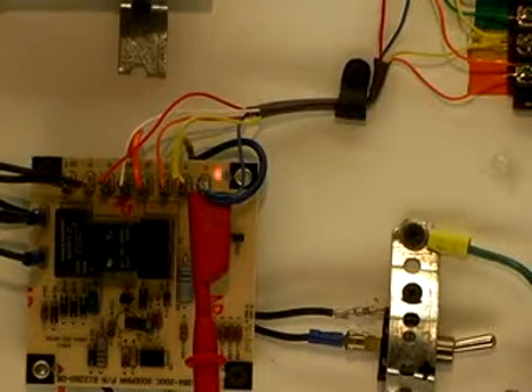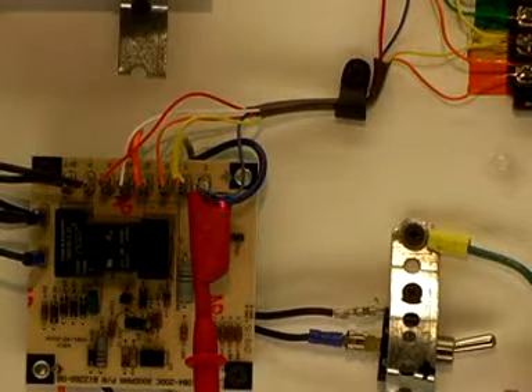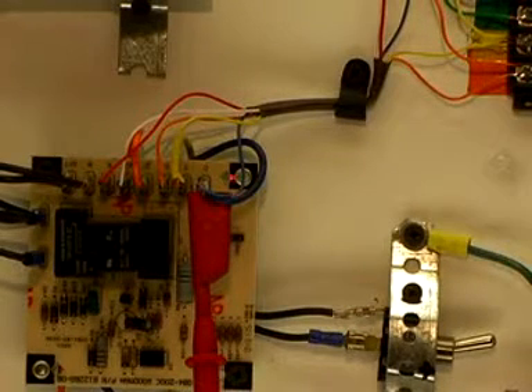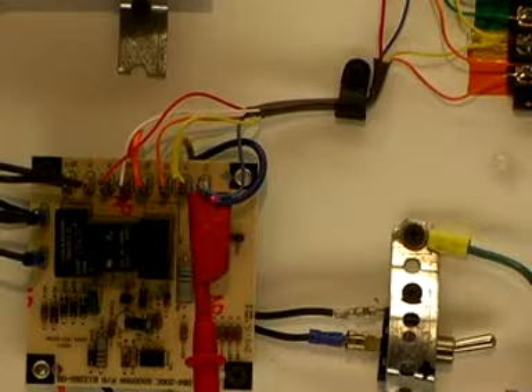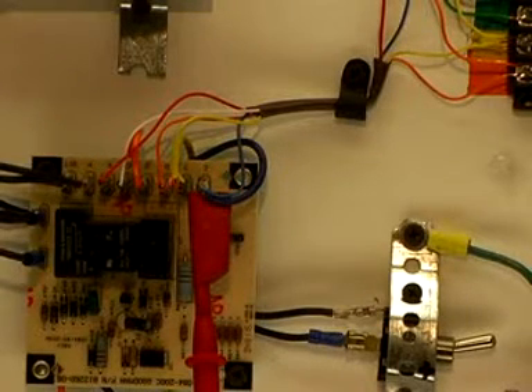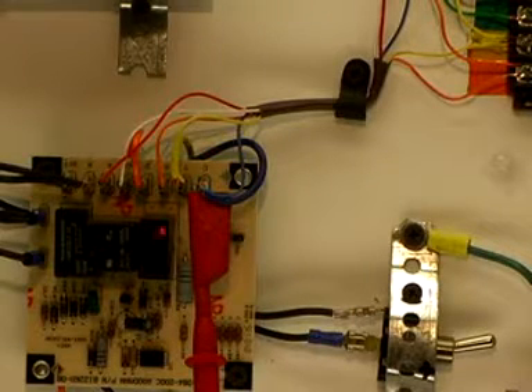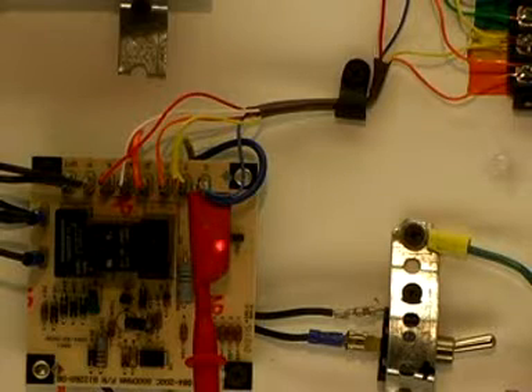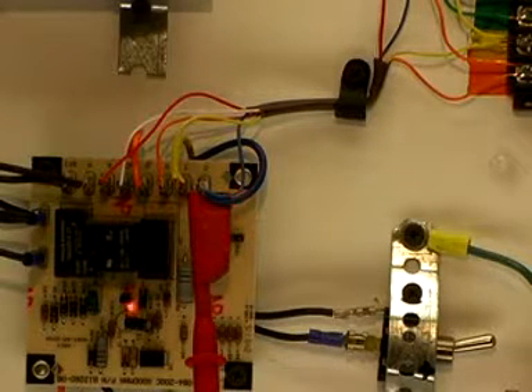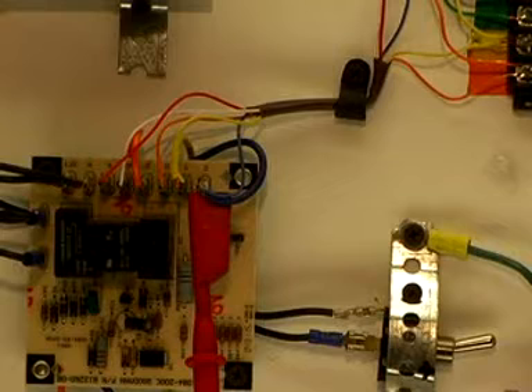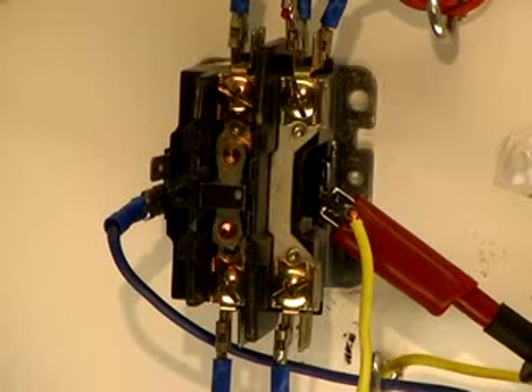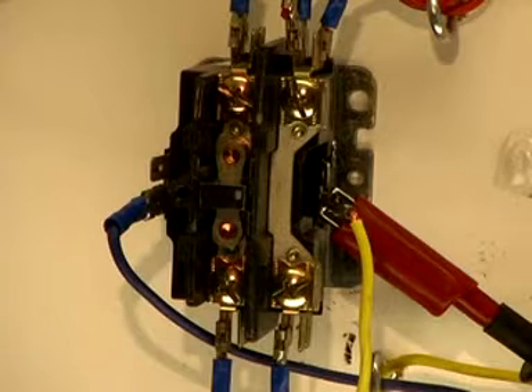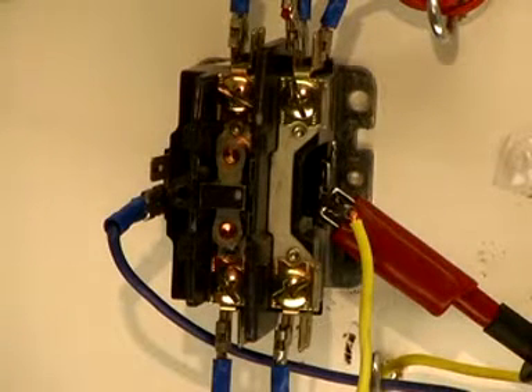So we've attached one of our meter probes to the common terminal on the defrost board, or if there was a wire nut there, you could take the wire nut loose and hook up to the wire. But like I say, try to get as near to the air handler as you can with your common connection on the meter probe, so that you don't have to deal with opens in the common somewhere. Then our other meter probe is set up at the contactor. We already know we're not going to read any voltage, but anyhow, you've got to go to the contactor and see if there's 24 volts there. There's always a possibility that the contactor is bad. So let's see if the meter will tell us that we don't have any voltage at the contactor.